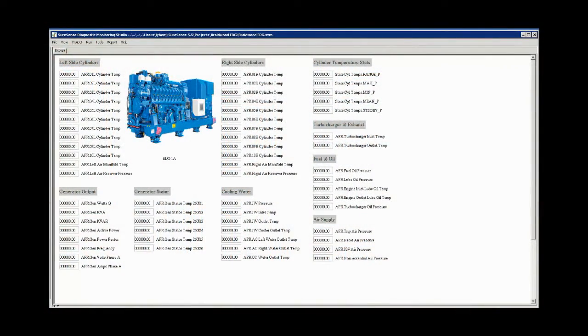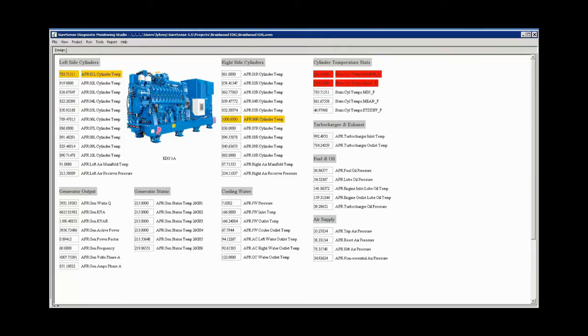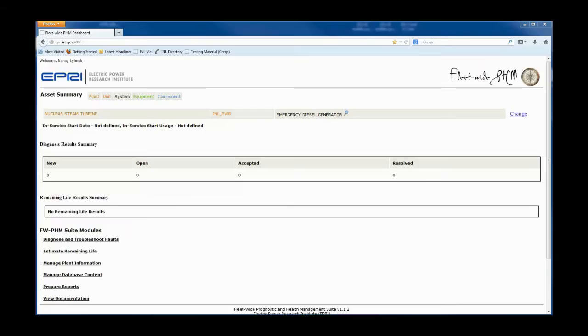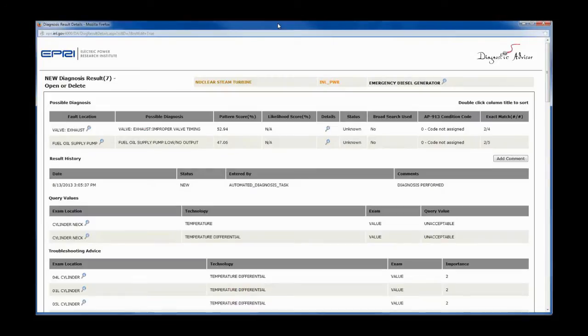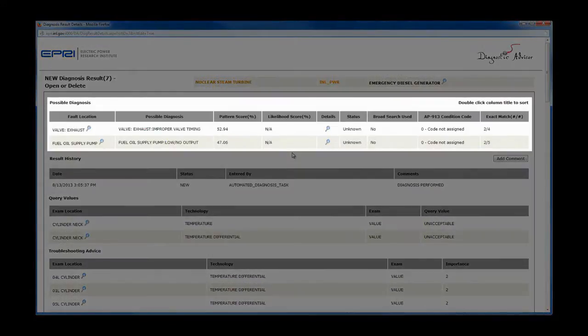The demonstration uses operating data from a 24-hour run of an emergency diesel generator. Simulation was used to mimic improper valve timing. The engine parameters are monitored and the alerts are created when the temperature range between the cylinders exceeds the recommended levels, or when one or more cylinders becomes too hot. The Diagnostic Advisor detects the newly indicated problem and creates a new diagnosis result for the diesel engine. Based on the available data, both improper valve timing and degraded fuel oil supply pump are indicated as likely faults.